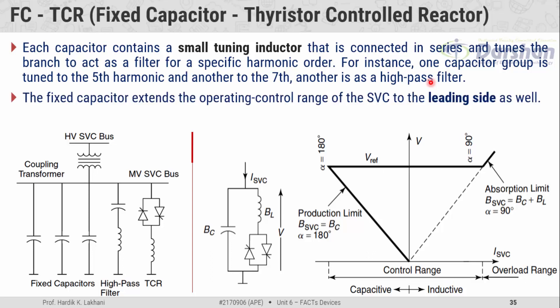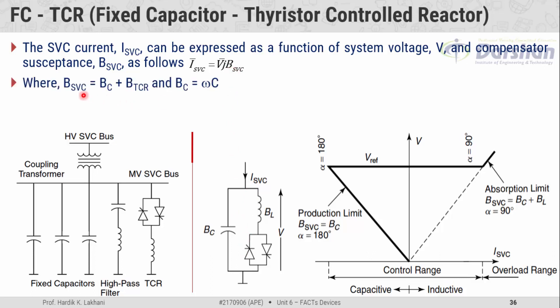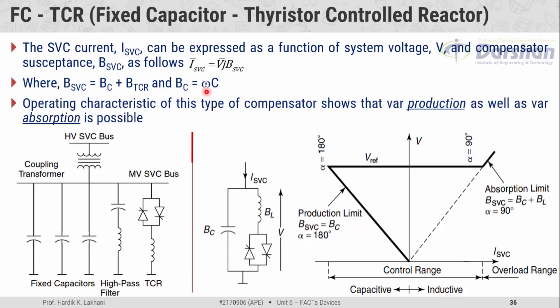The fixed capacitor extends the operating control range of SVC to the leading side as well. The SVC current I_SVC can be expressed as a function of the system voltage — the voltage across the compensator — and the susceptance B_SVC, which is the net susceptance offered by the fixed capacitor and thyristor controlled reactor. The current through the SVC depends on the magnitude of susceptance offered by the SVC, where B_SVC is the combination of susceptance offered by all capacitive branches plus susceptance offered by the reactive branch, and B_C equals omega times C.